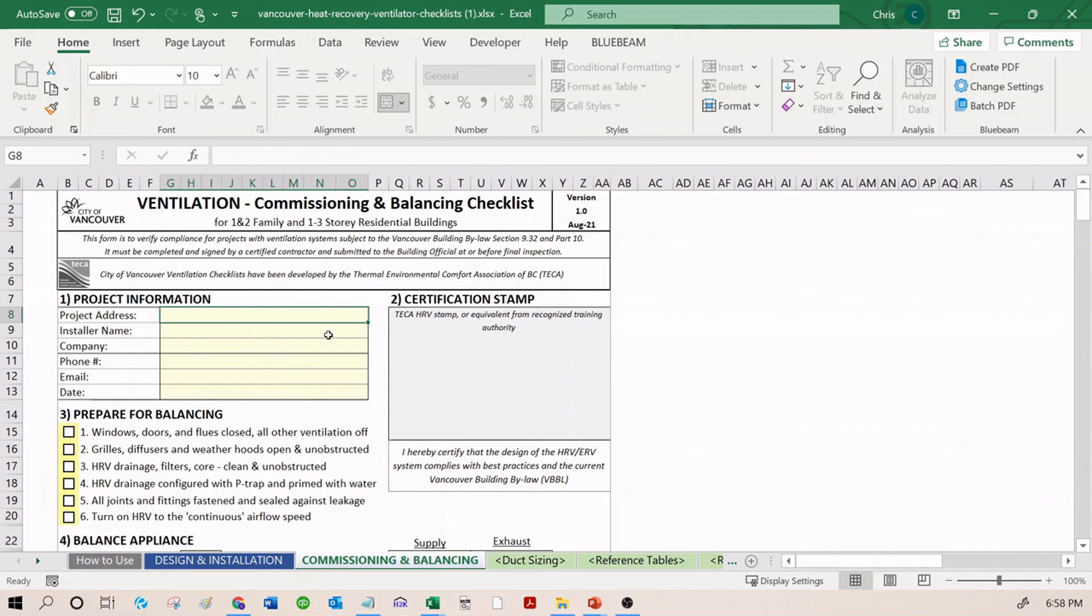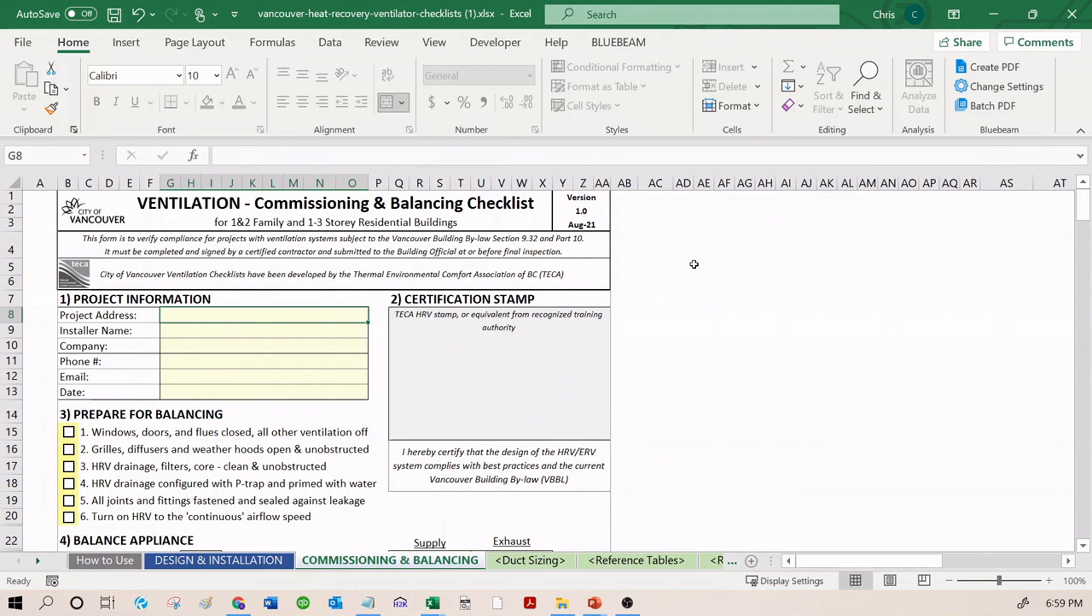I like to remind anyone installing and commissioning an HRV that this is as important as a health and safety issue. Inadequate ventilation can also be a silent problem. It's much different from inadequate heating because inadequate heating is going to result in a phone call right away and correction of the system. Inadequate ventilation is going to result in lack of fresh air to the building or excess moisture buildup. These problems are going to accumulate over time. That's why the City of Vancouver has adopted this fairly strict commissioning and balancing policy.